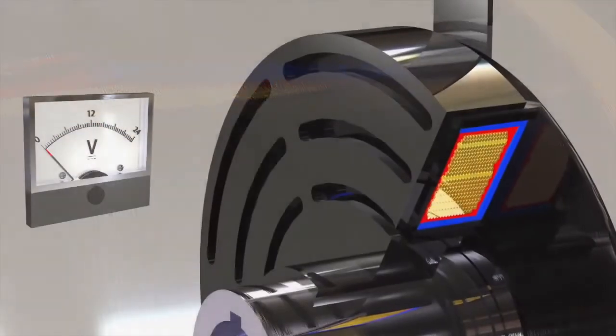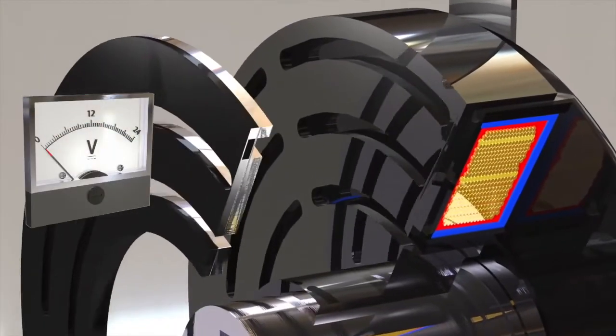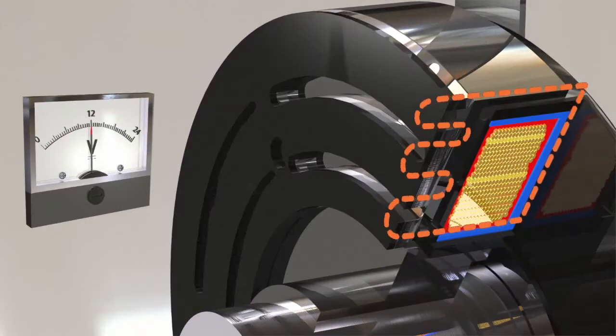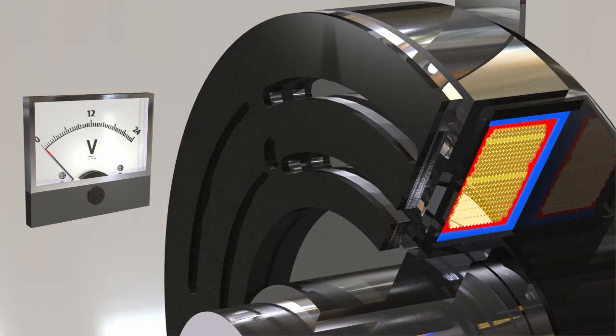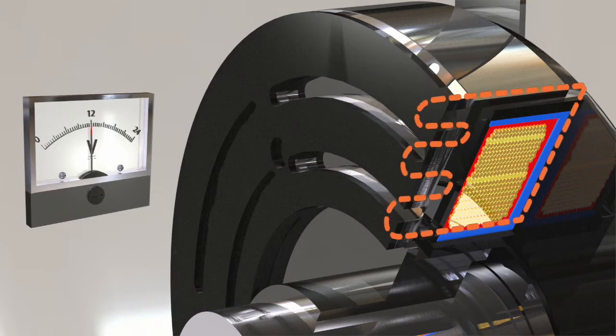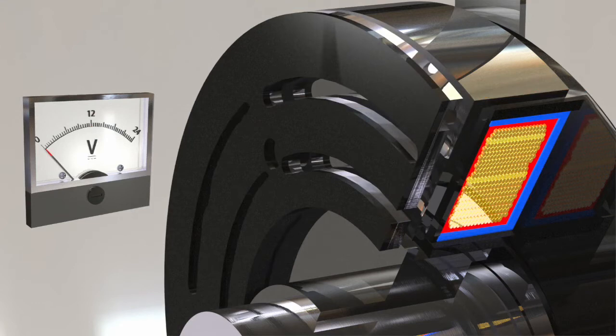When magnetic flux is created in the field coil, it goes into the rotor, which has a number of slots. On the corresponding armature, similar slots are made, which forces the flux to travel in a north-south pattern, looping across the armature and rotor face. These multiple points of contact increase the torque output of the clutch, reducing weight and size.